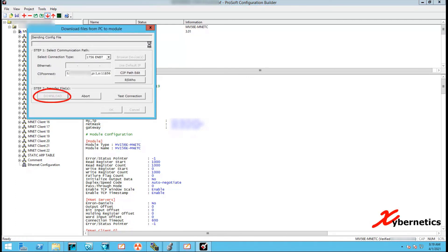Next, click on the red arrow pointing downwards — a window will pop up and you click the Download button. The configuration file will start to get transmitted into the module. Once that is complete you'll get a 'download complete' message, and the module power cycles by itself. Once the power cycle routine is complete, a 'module running' message will pop up. That is how you change the IP address of the ProSoft module.